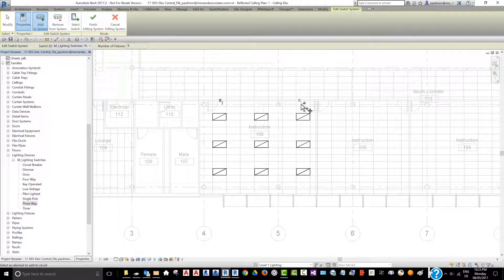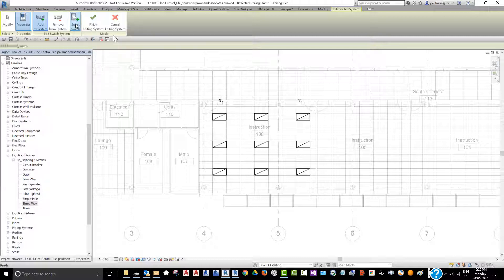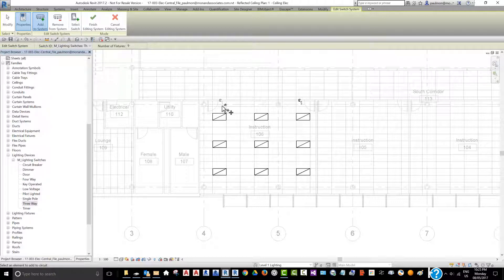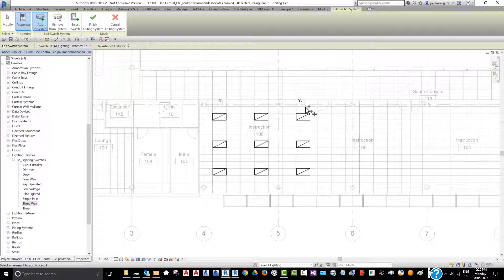If we try to select the yellow 3-way switch, you can't. If we try to Select Switch and allow this switch by clicking Switch, we are disassociating the other switch from this switch circuit. So we can only select one light switch per switch circuit. At this point in time, Revit 2017 does not have the provision to include two light switches in a switch circuit.